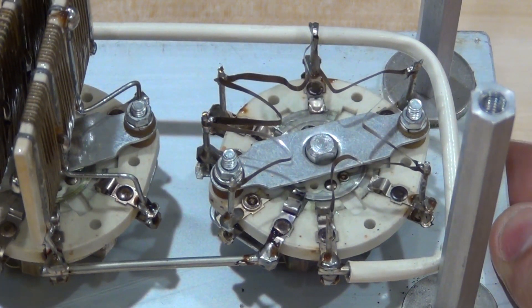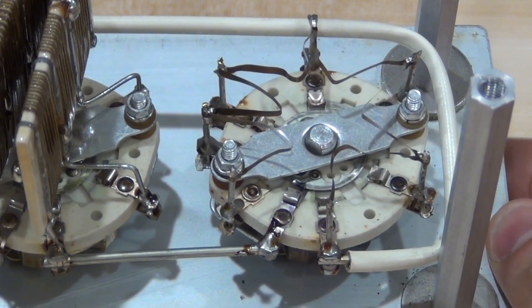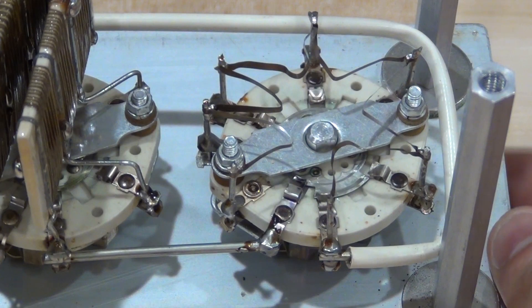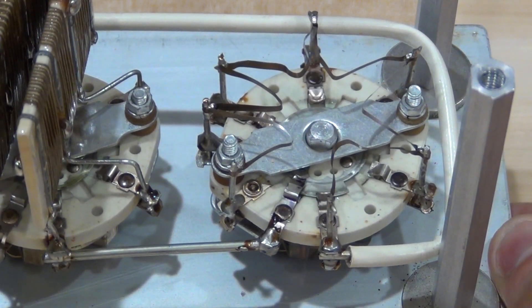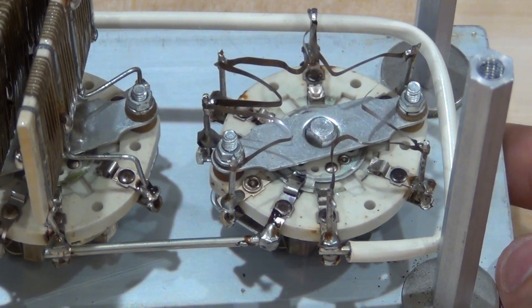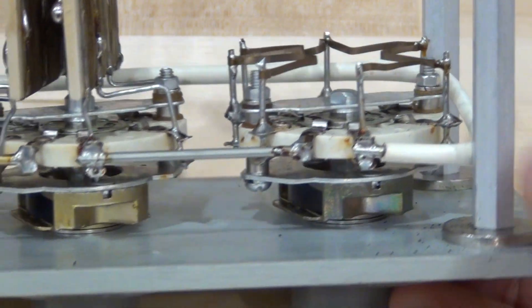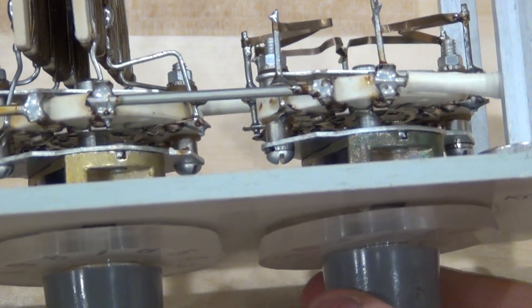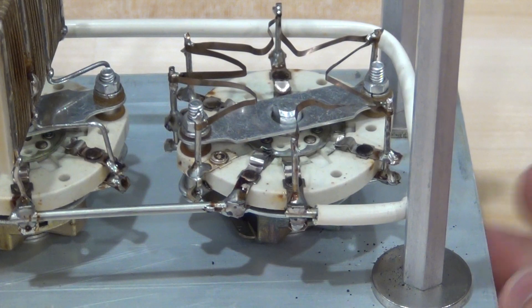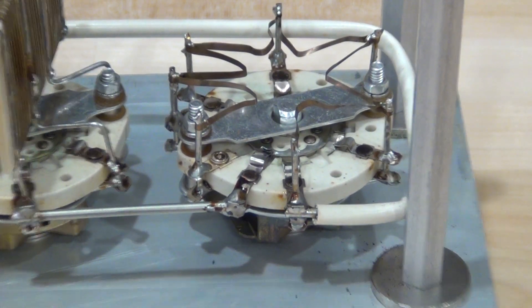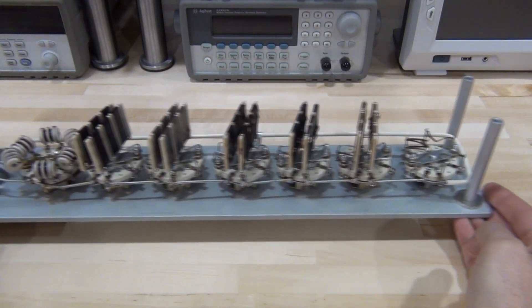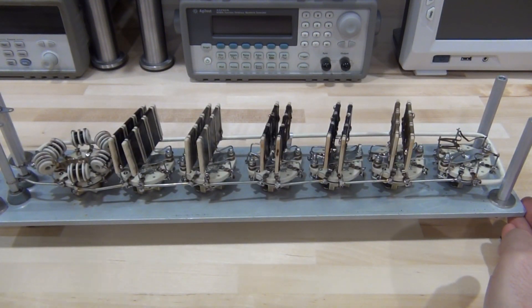If you take a close look at this one, you can get an idea of what those contacts look like. If I go and rotate this you can see how the plate at the bottom will be rotating and making contact with varying sections of the 0.1 ohm resistors. There are contacts at the bottom too which are difficult to see, so I'm gonna have to spray both the top and the bottom. This is one scenario where a spray is very important because I have no real way of reaching the bottom.